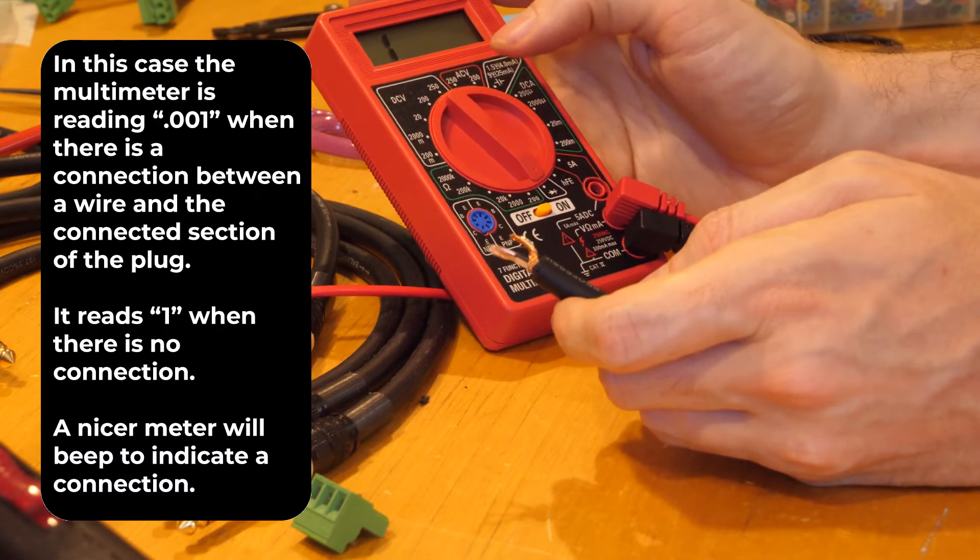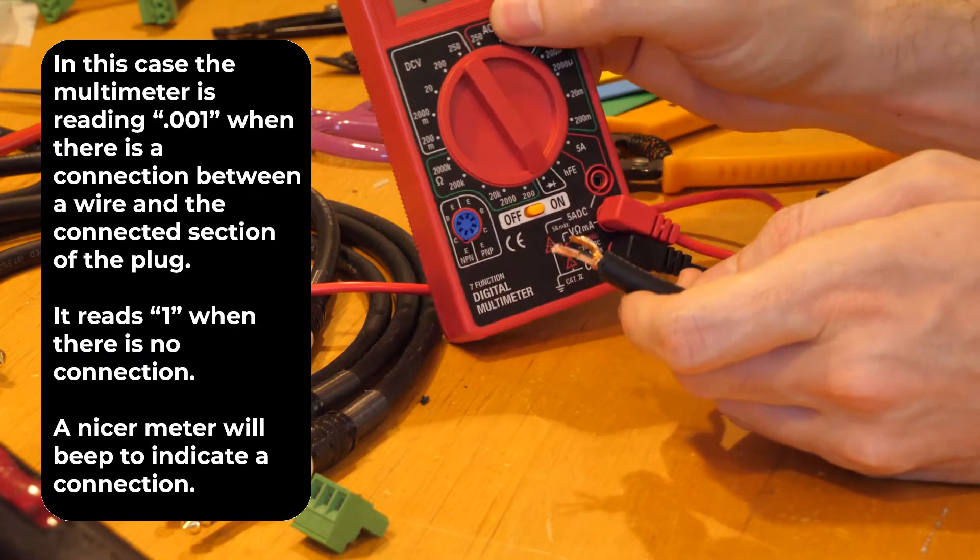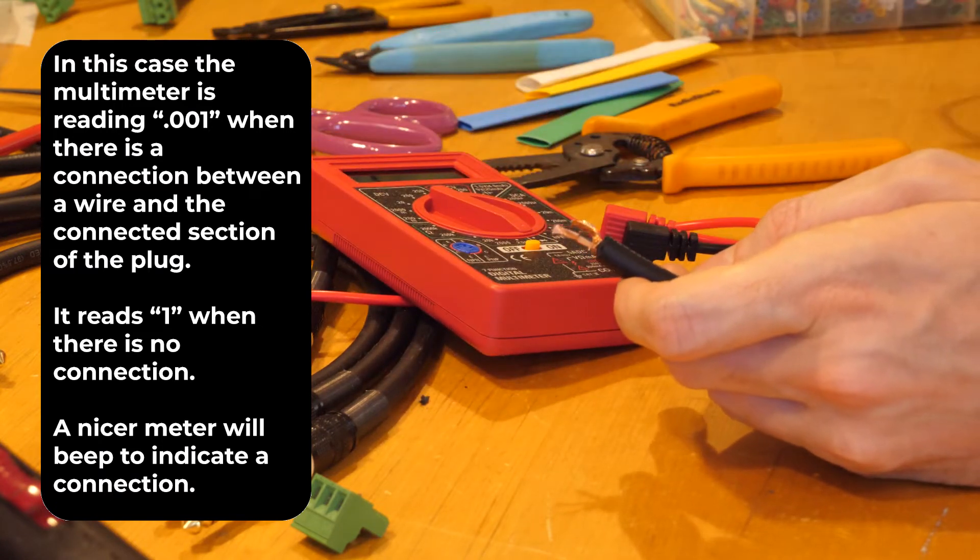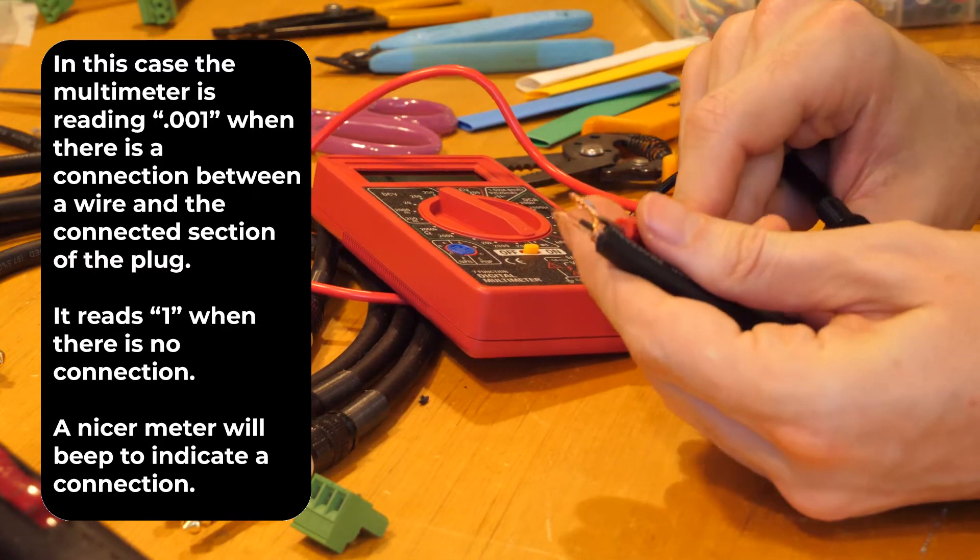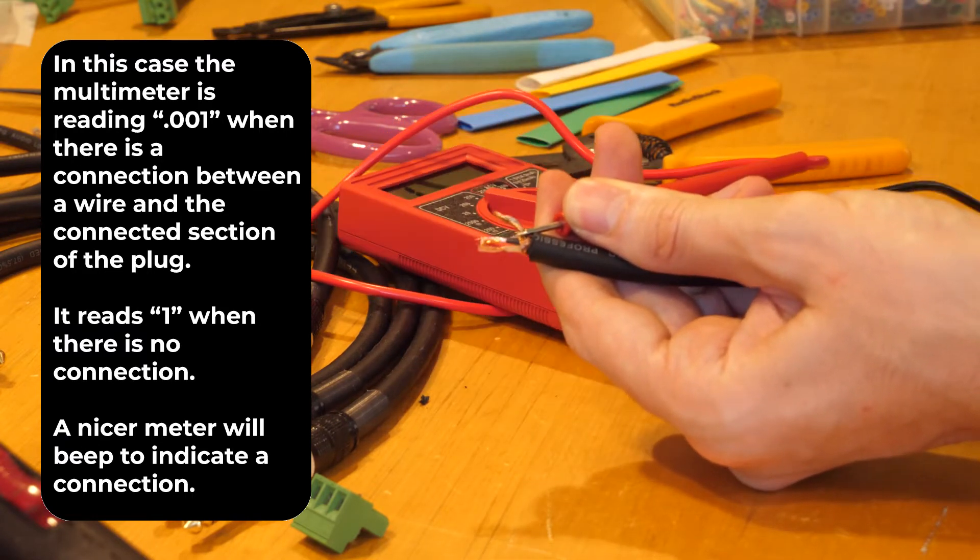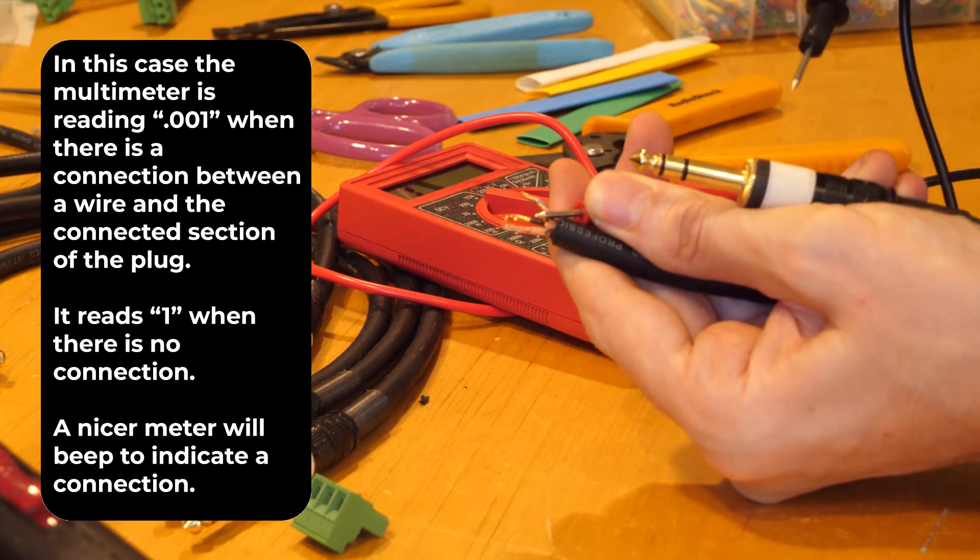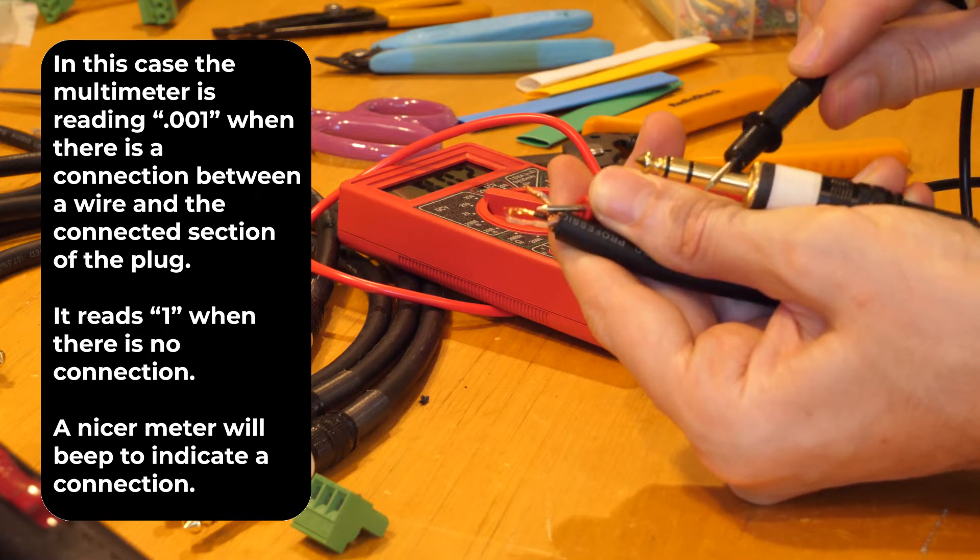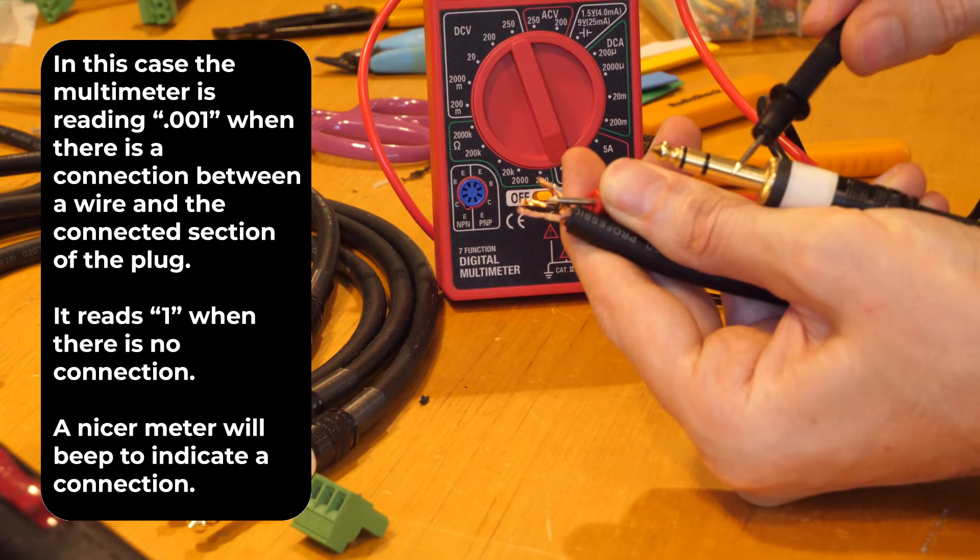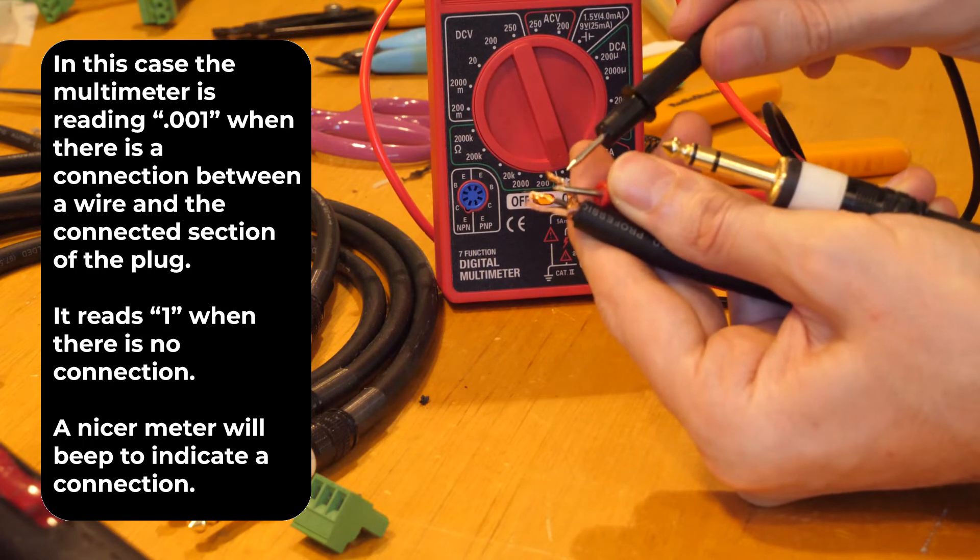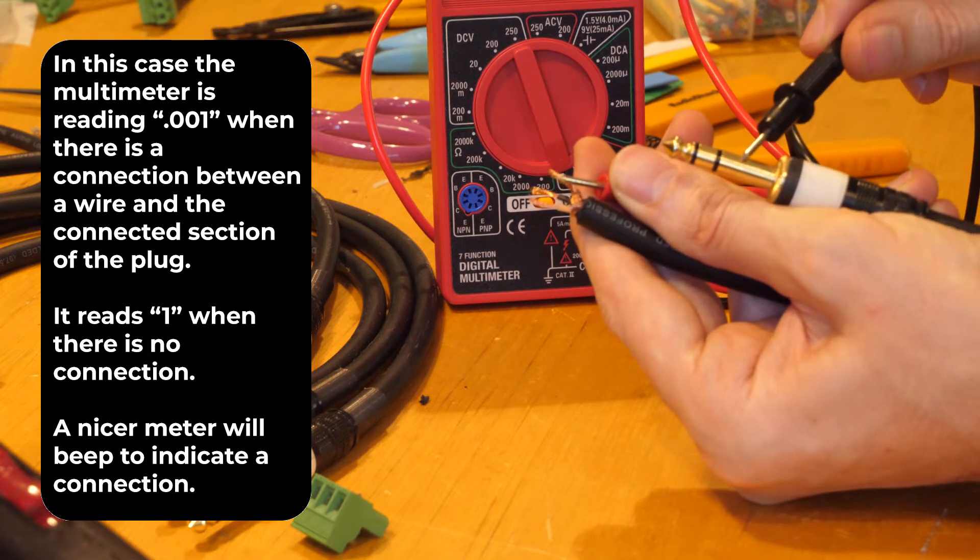But anyway, on mine, it just shows one when there's infinite amount of resistance between the two prongs. So I'm just going to get my two probes. I'm going to put one probe on the shield. And then I go over to here and I touched the shield part. You can see that the resistance goes down to almost zero. So you can see the resistance goes down to almost zero. So that shows that this drain, this shield is correctly mapped to this part.